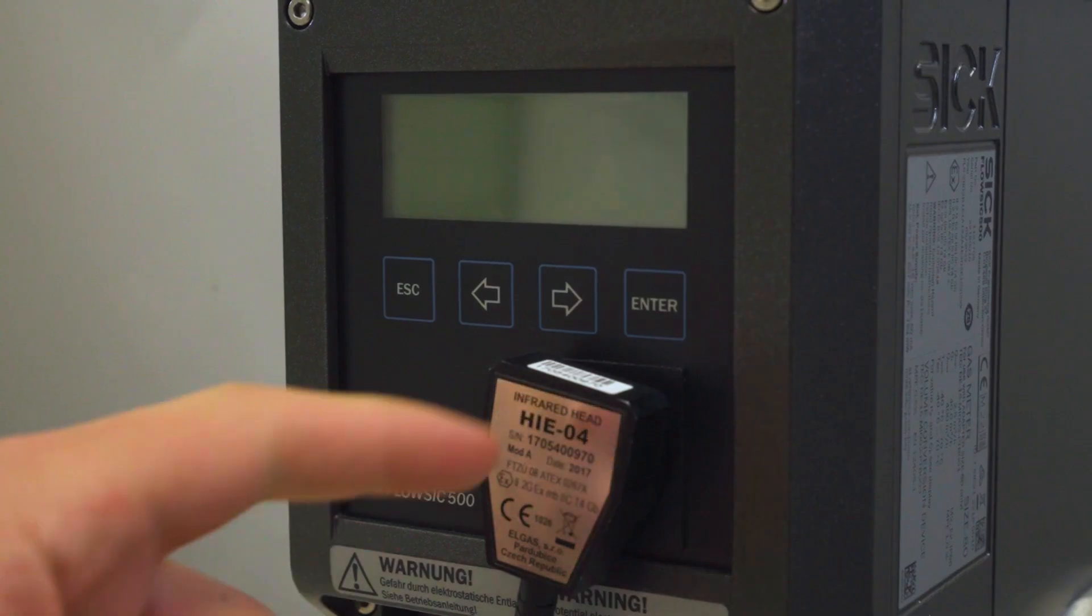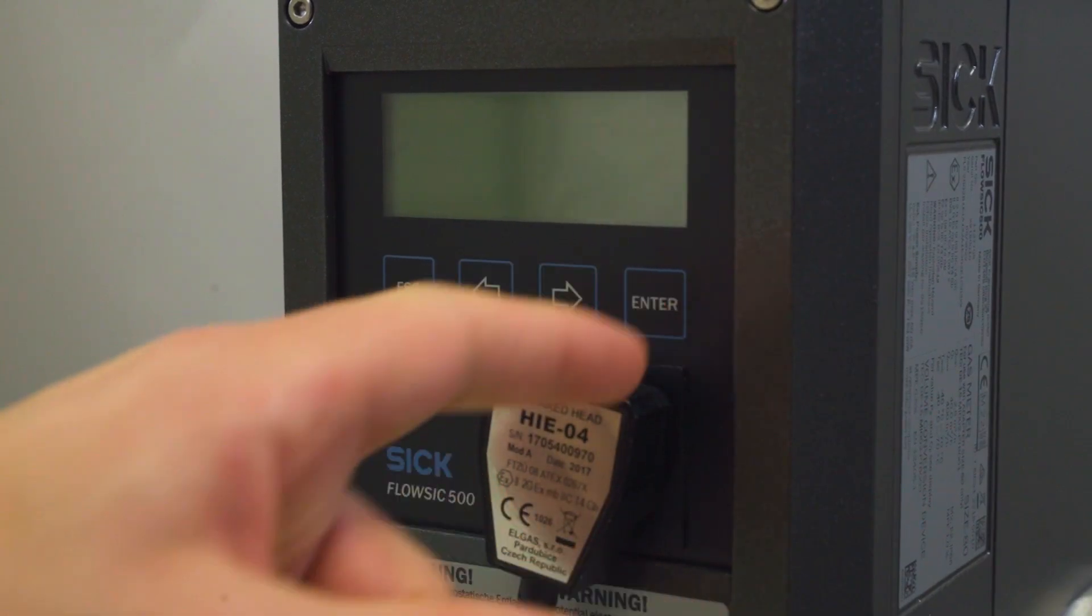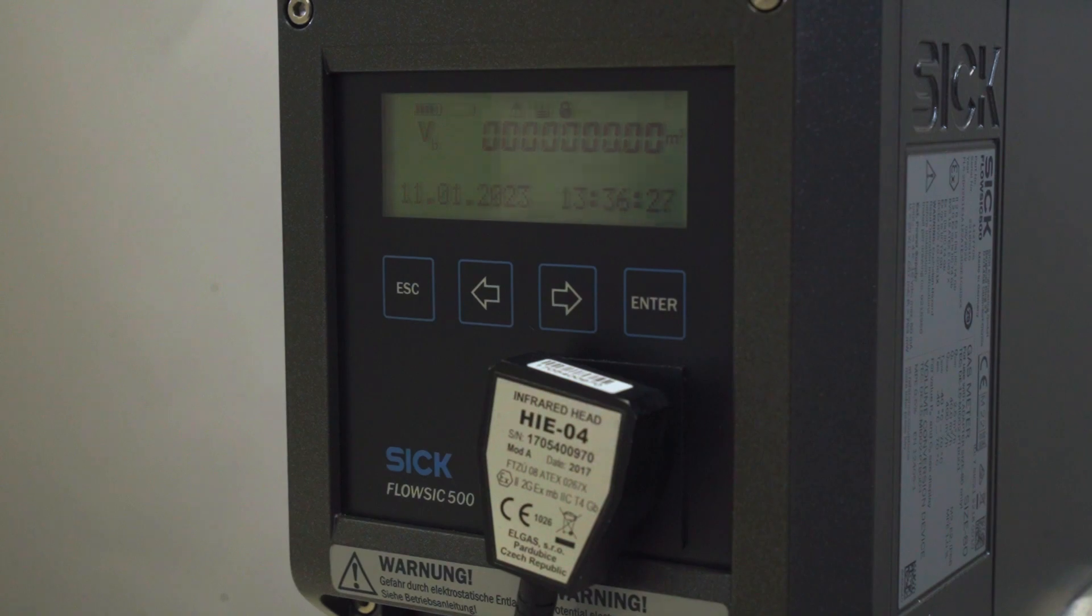Connect the USB plug to your PC and add the adapter to the optical interface of the FlowSIC 500. Press any button on the display to activate it. This will also enable the optical interface. Now you can establish a connection via FlowGate. This connection remains active until you remove the infrared USB adapter.